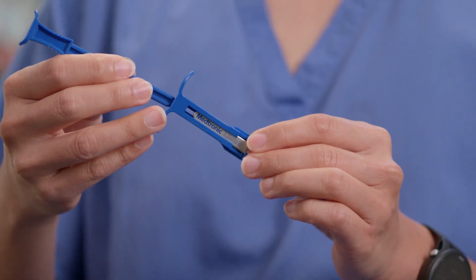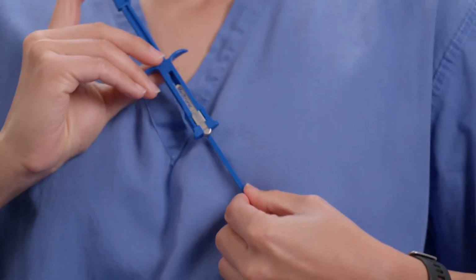So the implantable loop recorder, which we recognize as being a small device, smaller than the size of your little finger, is normally fed into an injectable device here, which is the introducer. And the implant is done by inserting this small plastic sharp introducer just inside of your skin under local anesthesia, and a plunger, or the aspect of the device that pushes the device through, and so the device comes out within your chest wall, and it's implanted like that, and so it sticks inside of your chest when the plunger is removed.